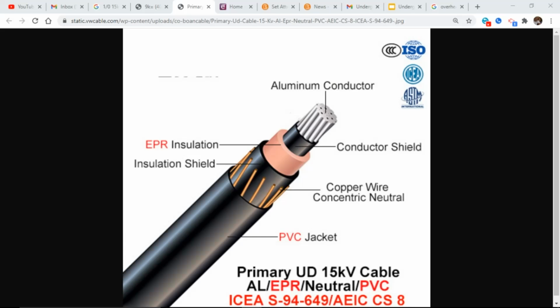So inside a transformer, if you're moving elbows around, and remember inside the single phase pad mount transformer, I'll bring up a picture in just a moment. If you're moving conductor around inside a transformer and this makes contact with one of the secondary lugs, consider it as making contact from neutral to 120 volts, and it will make a pretty good explosion right there. So make sure you maintain clearances from this PVC jacket to the secondary bars and anything else inside the transformer.